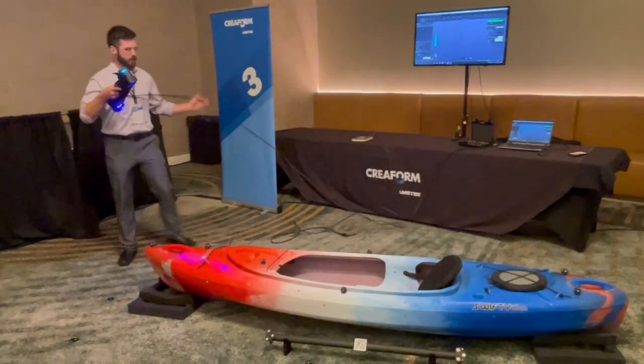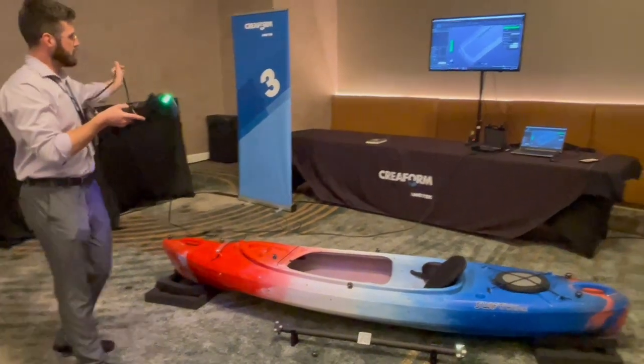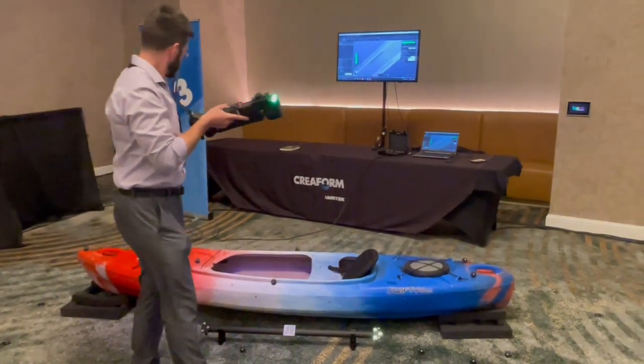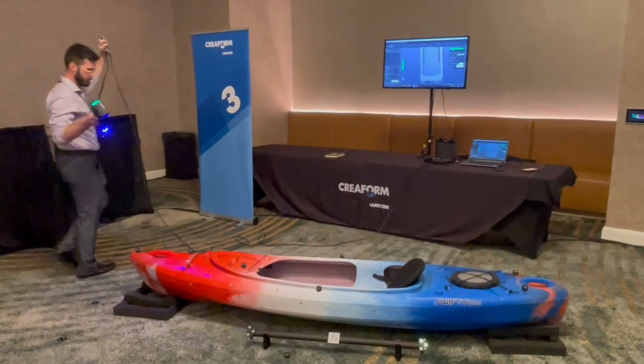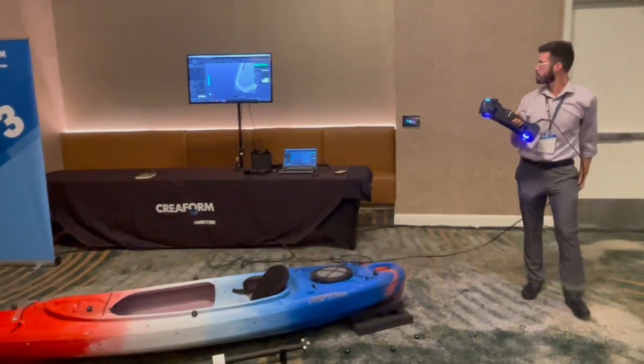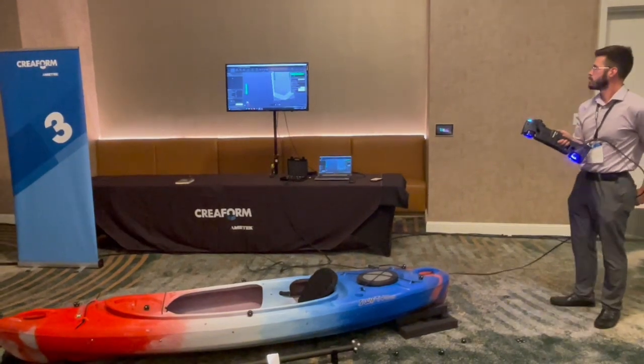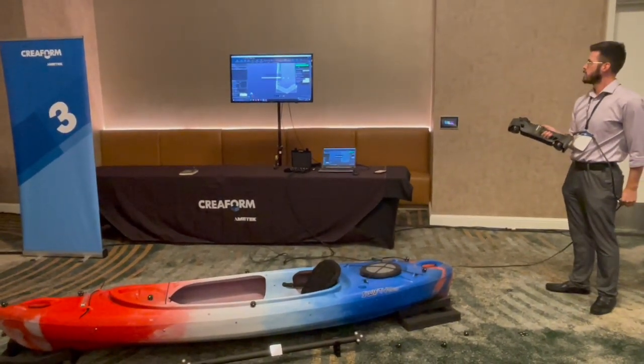This gives us a two-meter standoff. You can see the calibration bar there. If you want to calibrate live in the scanning session you can do that — just set the calibration bar there and you're ready to go. You can also do it the standard way, scanning the calibration bar before your scan. This guarantees that every user has a calibration exactly when you need it, so calibration drift isn't really a problem anymore.